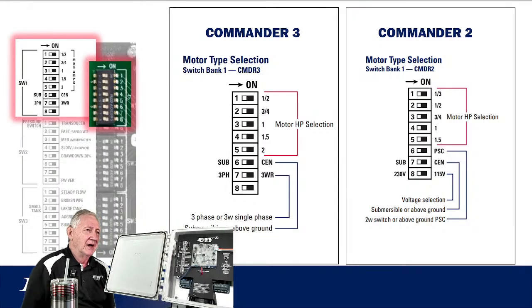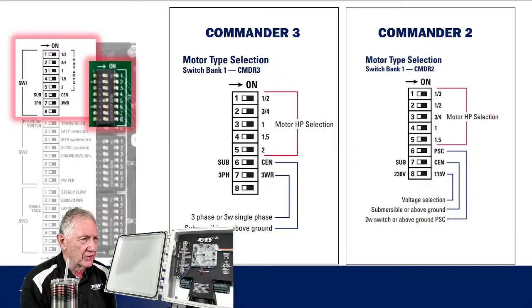And I had mentioned that there are some slight differences between the Commander 2 and the Commander 3. So if you look at the top bank up there, in position number 6, under the Commander 3, you have a choice. You can either set this up to run a submersible pump motor, or you can set it up to run a centrifugal pump motor. Those switches, in order to be on, have to be in the right-hand position.